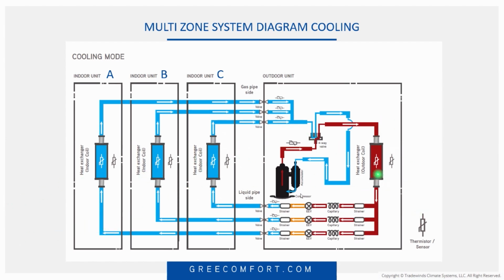What if this machine is low on refrigerant? If I've got all three running, and let's say I'm running in cooling mode, and we talk about this all the time, don't we, JD? 20 to 25 degree TD, right? Yep. So our air entering and our air leaving, if we're about a 4 degree demand, in other words, let's say it's 75 degrees in the house and we set it at 70, 71 degrees, we've got a 4 to 5 degree temperature demand, right? Right. So once you have that 4 to 5 degree temperature demand and you let the machine run for a little bit, if you measure your return air temperature going into that indoor wall mount and out of that wall mount or ducted unit or whatever else you're working on, you should have a 20 to 25 degree temperature difference across it.